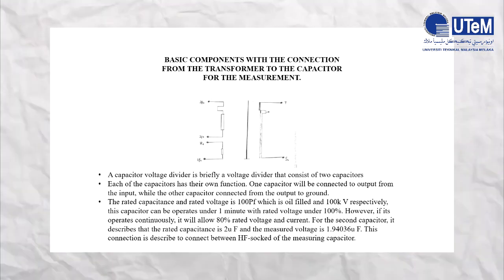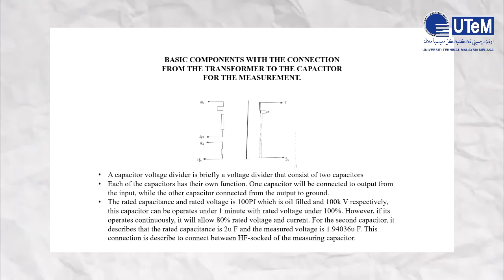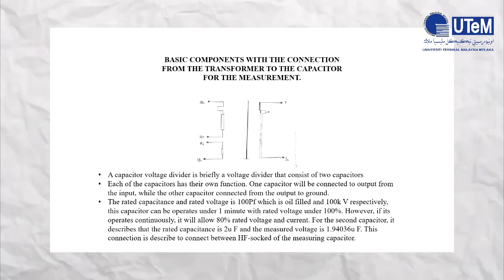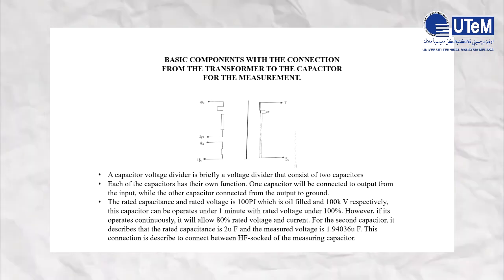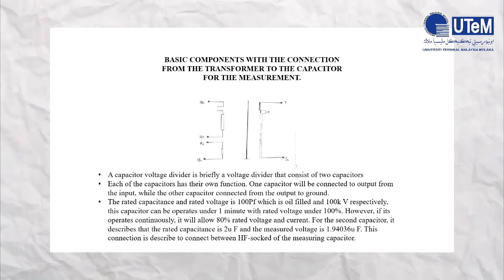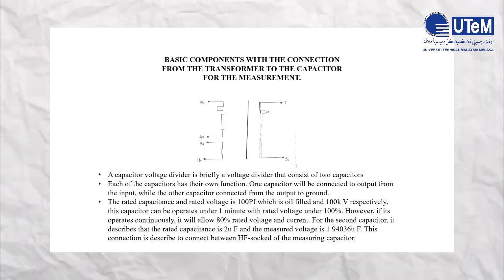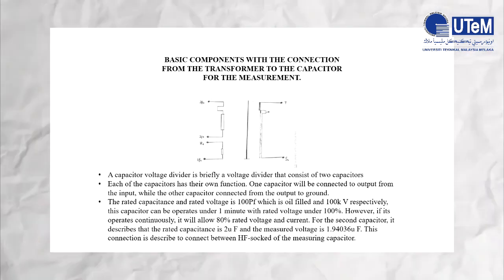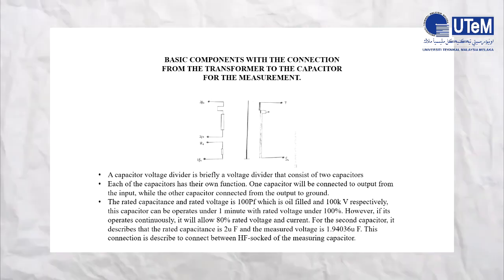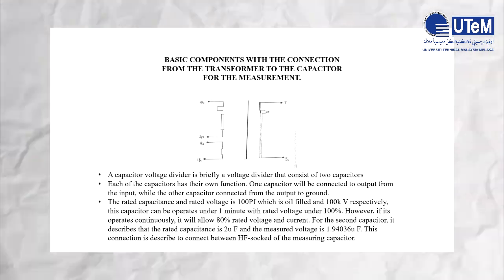A 100 picofarad capacitor, oil filled, with a rated voltage of 100 kilovolt, operates for 1 minute under 100% rated voltage, but if it operates continuously, it will allow only 80% of the rated voltage and current.